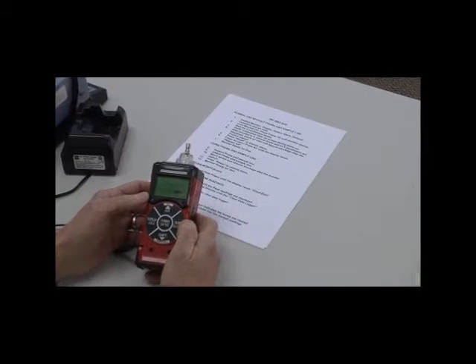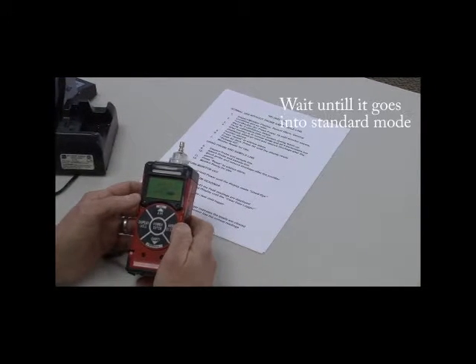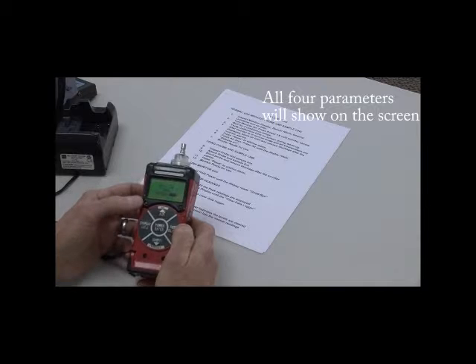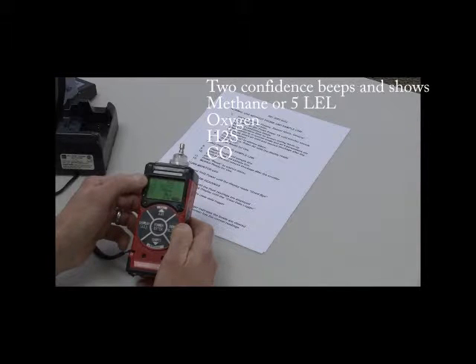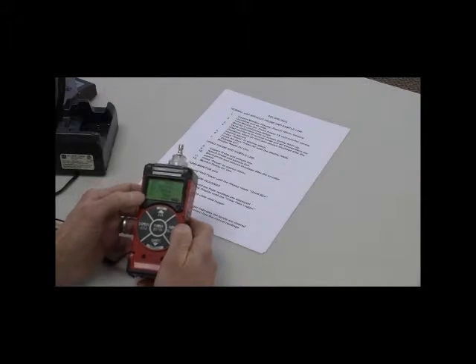At this point, I'm going to wait until it goes into standard mode. At that time, all four of the parameters will show up on the screen, and it gives me two confidence beeps. Here we have the four parameters: methane or percent LEL, oxygen, hydrogen sulfide, and carbon monoxide.